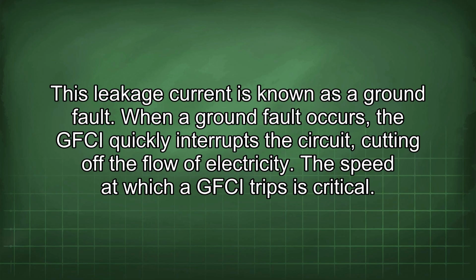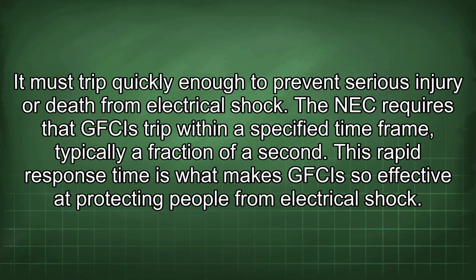This leakage current is known as a ground fault. When a ground fault occurs, the GFCI quickly interrupts the circuit, cutting off the flow of electricity. The speed at which a GFCI trips is critical. It must trip quickly enough to prevent serious injury or death from electrical shock. The NEC requires that GFCIs trip within a specified time frame, typically a fraction of a second. This rapid response time is what makes GFCIs so effective at protecting people from electrical shock.